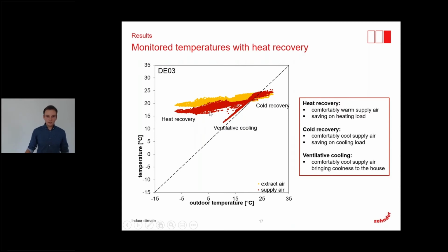So what we can see here in winter, we are using the heat recovery and we get the supply air to a comfortable level. So here we save energy on the heating load of a house. When it gets warmer, we begin to open the bypass. So we have energy savings due to ventilative cooling, which you can see in these red dots. And if we go further, we can see a change. The outdoor air is getting warmer than the inside air. So we switch back to the heat recovery, or I should rather say cold recovery. So here we recover cold and save energy on the cooling load of a house.